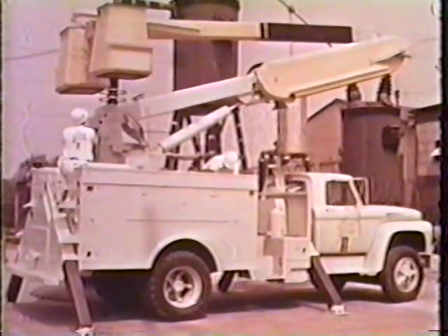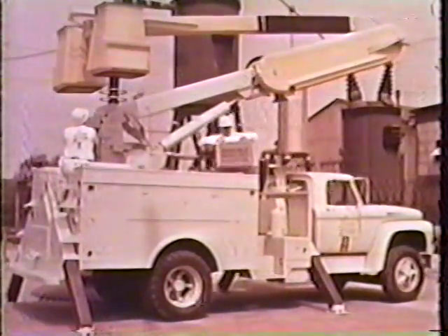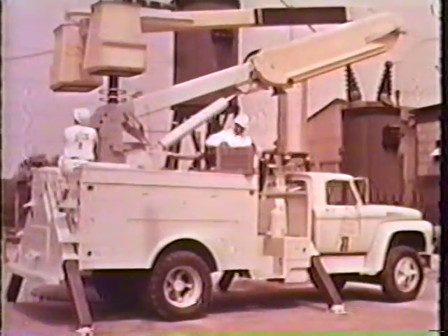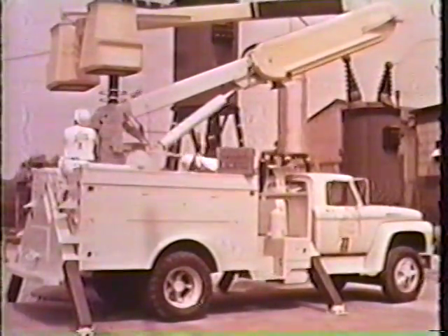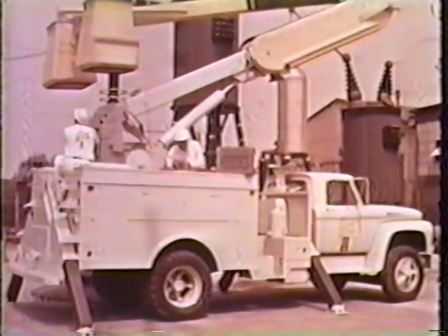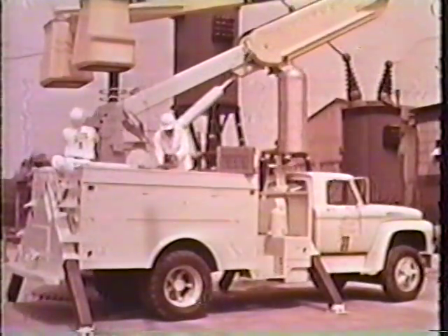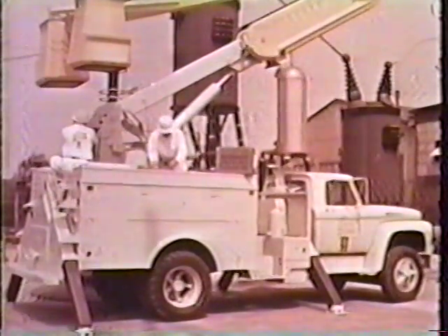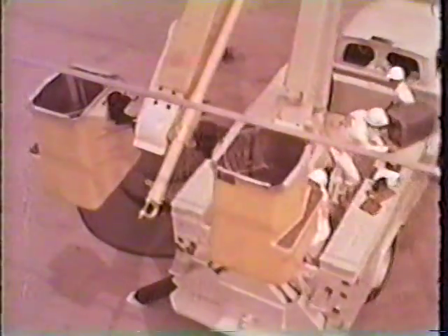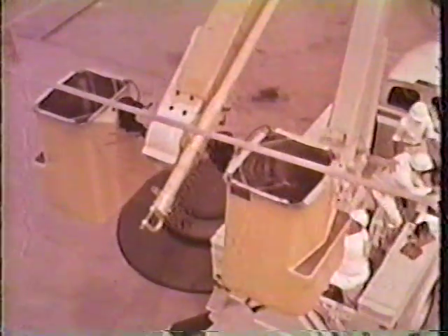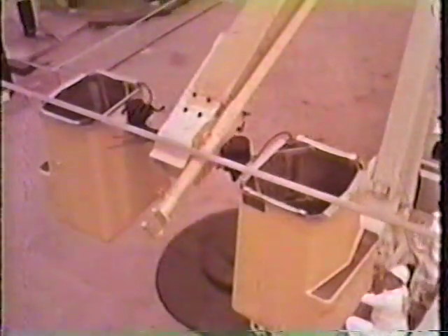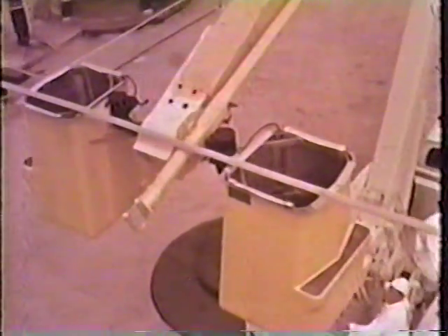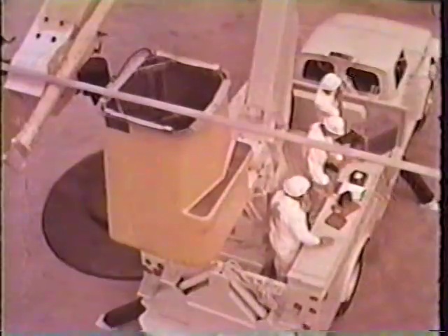The meter used in the laboratory certification test is equivalent to that available for use with the boom in the field. Frequently, other meters and equipment may also be used to verify the condition of the insulation. Using controls at the base of the boom, the empty buckets are raised until the shielding makes contact with the conductor. This is the procedure recommended for all tests in the field.